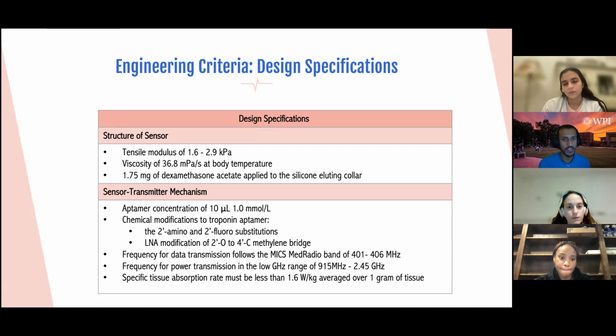An optimal frequency range for data transmission and power transmission must also be considered for the chip to transmit data and power the sensor. Therefore, the frequency band for the data transmission will follow the medical implant communication system MedRadio frequency band. For wireless power transmission, the frequency band is in the low gigahertz range and has been identified as the ideal range to power the sensor as it provides minimal power loss due to tissue absorption.